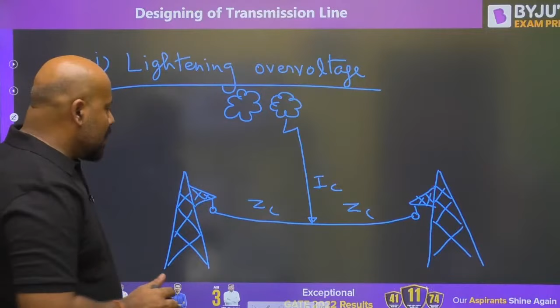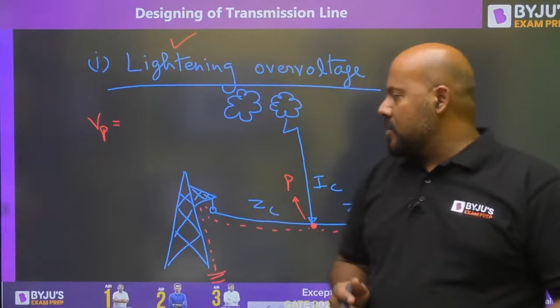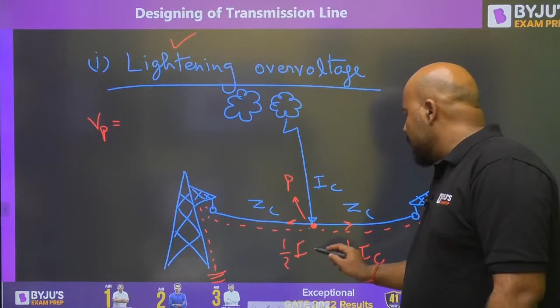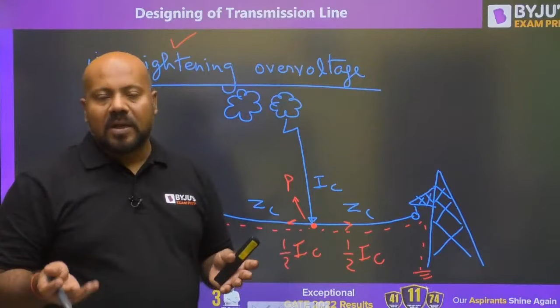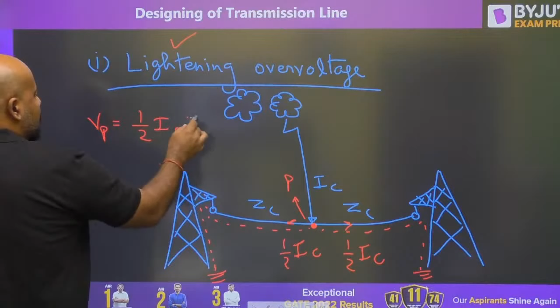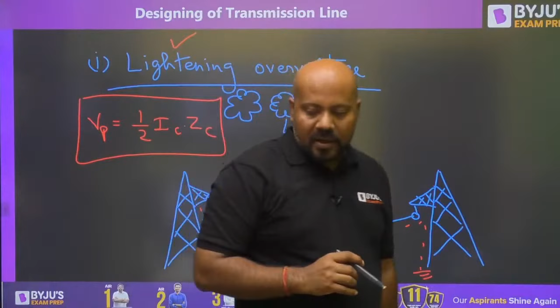Now if you want to see what kind of lightning over voltage may be present in your system, let's say this is point P. What is the maximum possible over voltage which may be present? If this is IC, then the current going into these two paths is going to be 1/2 IC and 1/2 IC. The reason is that the impedance seen by the discharge current towards both sides of the conductor is the same, that is the surge impedance. So this discharge current is divided equally. So the potential of this point P where the discharge has occurred is going to be 1/2 IC into ZC. You may get a direct question on this concept in the GATE examination.